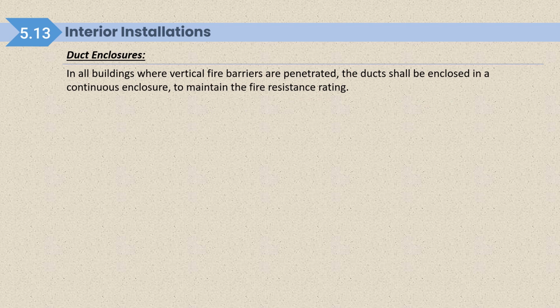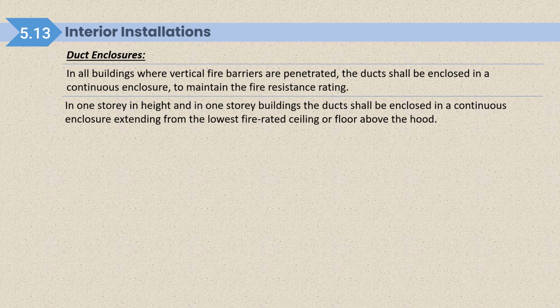Interior installation: in all buildings where vertical fire barriers are penetrated, the duct shall be enclosed in a continuous enclosure to maintain the fire resistant rating. In a one-story building, the duct shall be enclosed in a continuous enclosure extending from the lowest fire rated ceiling or floor above the hood. So this is mainly talking about the penetration when we pass the duct from one floor to another floor, or from one side of a wall to the other side. In that case, the penetration should be ensured to meet the same integrity of fire resistance.